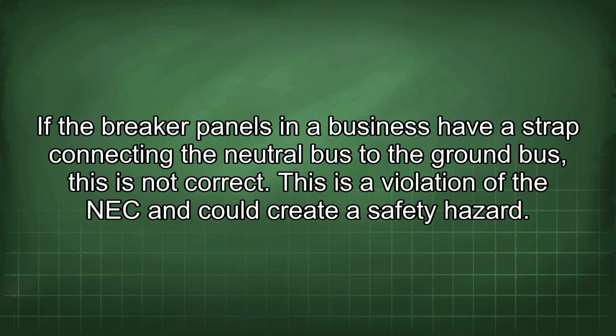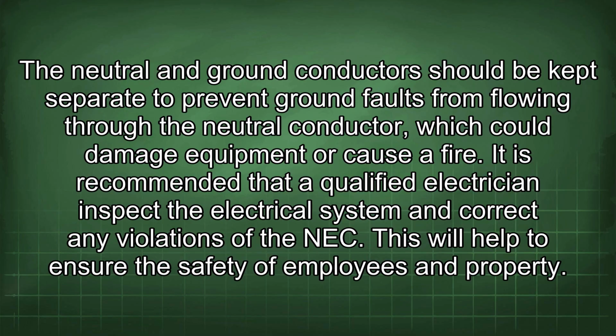If the breaker panels in a business have a strap connecting the neutral bus to the ground bus, this is not correct. This is a violation of the NEC and could create a safety hazard. The neutral and ground conductors should be kept separate to prevent ground faults from flowing through the neutral conductor, which could damage equipment or cause a fire. It is recommended that a qualified electrician inspect the electrical system and correct any violations of the NEC. This will help to ensure the safety of employees and property.